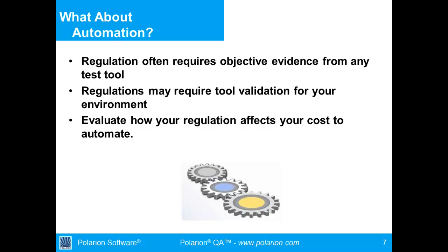Yeah, essentially what they're saying is that you have to qualify the installation process, and then you're qualifying the feature functionality and the production qualification. IQ, OQ, PQ, let's do them in order. Installation qualification, so you're confirming that you can install it. Operational qualification, OQ, which is confirming that the feature functionality that's asserted by the vendor and that you're using, usually against some type of publication, user pubs, or against a requirements document if you're lucky enough to have access to that.